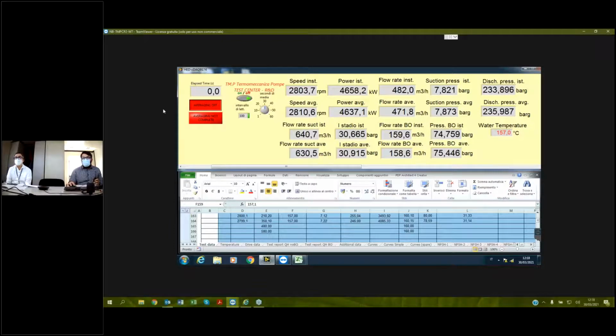So this test has been done regulating the water temperature, with the system previously presented by my colleague, at the design water temperature, which is equal to 157 degrees C. In 5-10 minutes we can show you how this procedure can be applied and how the system works. So Davide is going to make 3 points, 2 at full speed and 1 point at low speed. This is just to figure out how this system works.